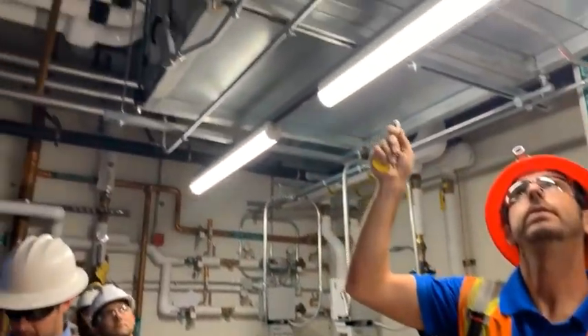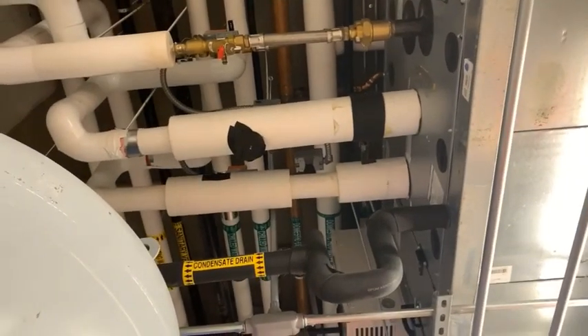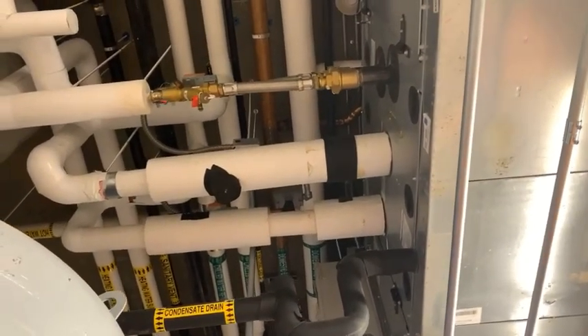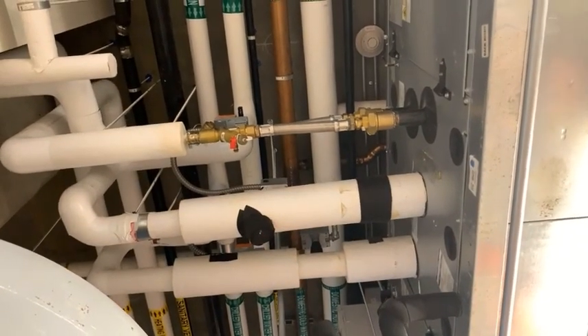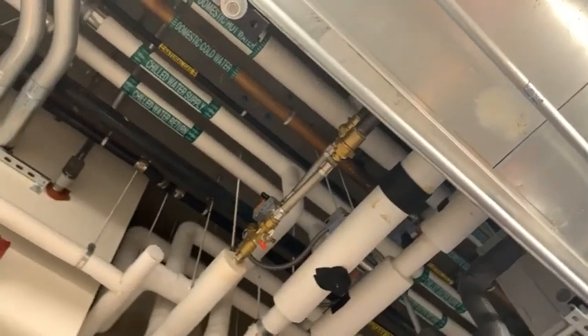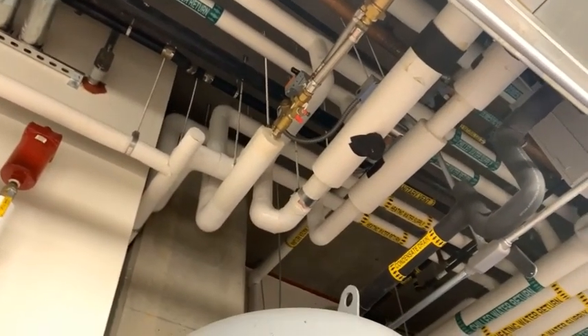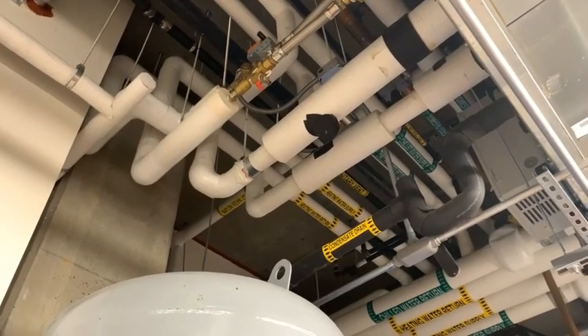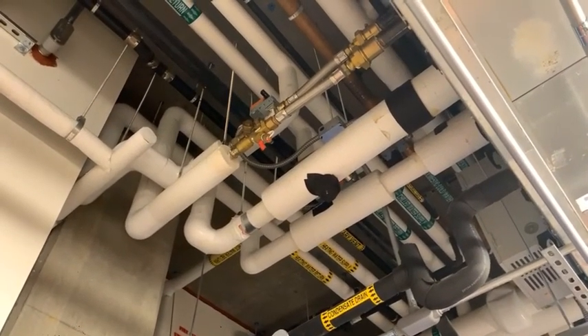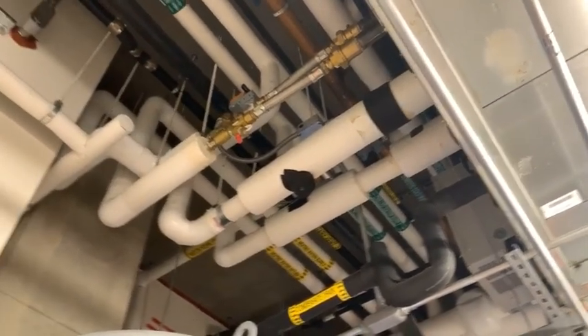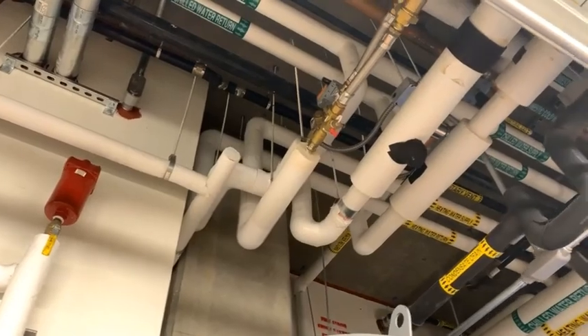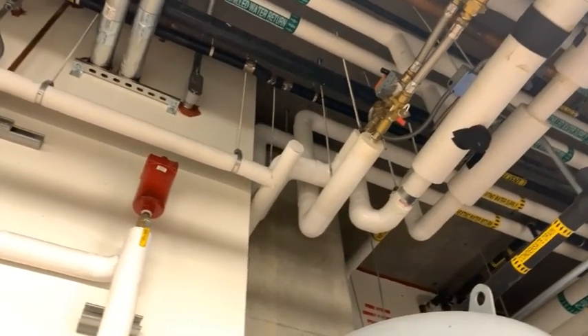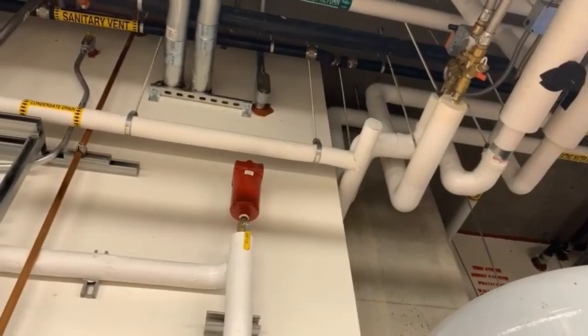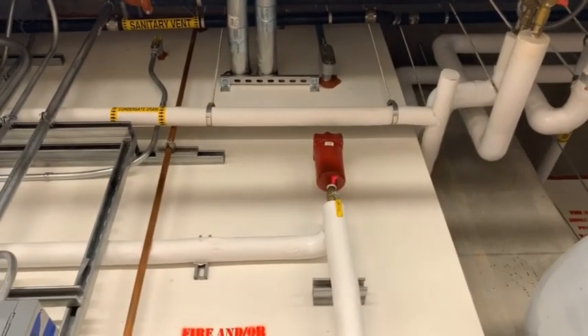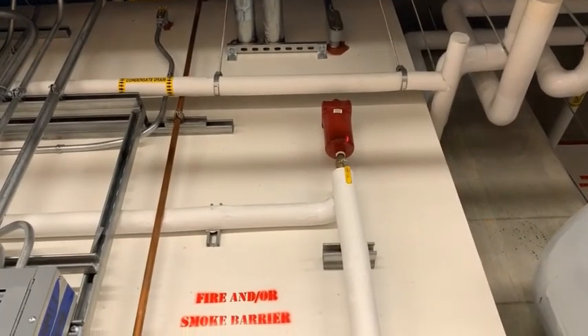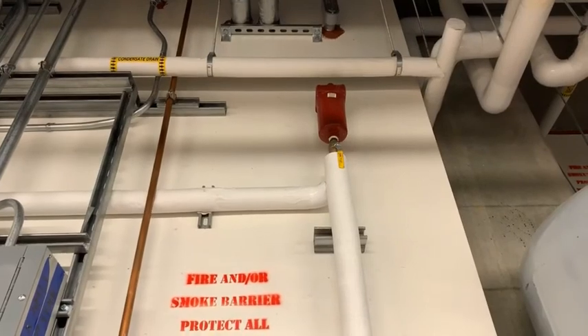Above me is an air handler. This air handler feeds segment 1 of first floor. This is just for the hose kits. So we have a hose kit on the heating and a hose kit on the chilled, okay? Control valve. This is the auto flow right here. And we have a strainer on the supply. The auto flow and the control valve are on the return. Okay. Screen. Shut off valves on there. On the expansion tank, so we don't trap air in the loop, we have an air vent right here. Keep this valve open at all times unless you're doing any maintenance on this air vent. But we want to keep this valve open at all times.